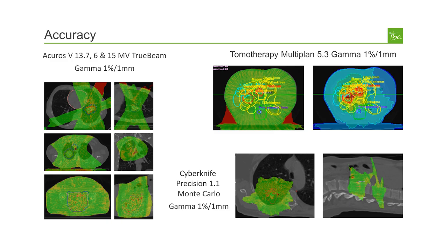A similar validation study was performed against the CyberKnife Precision 1.1 Monte Carlo dose computation engine, and again very good agreement was found even with a gamma criterion of 1% / 1 mm. The tomotherapy validation was performed against the Multiplan 5.3 treatment planning system and again very good agreement between these two algorithms was found.